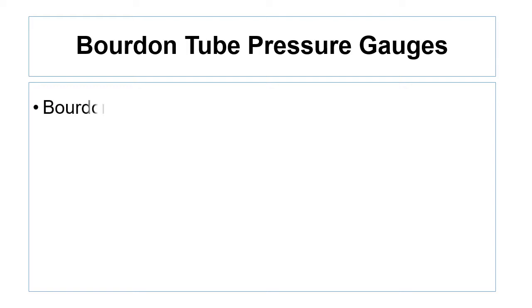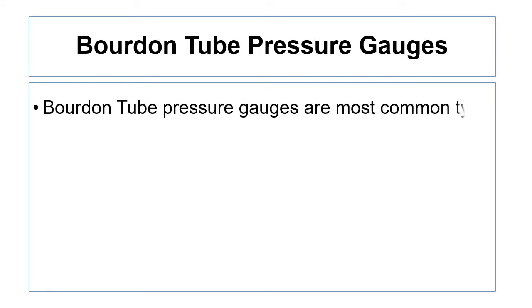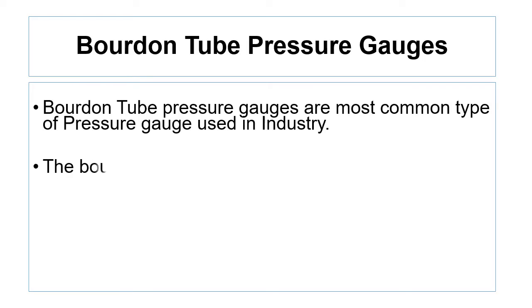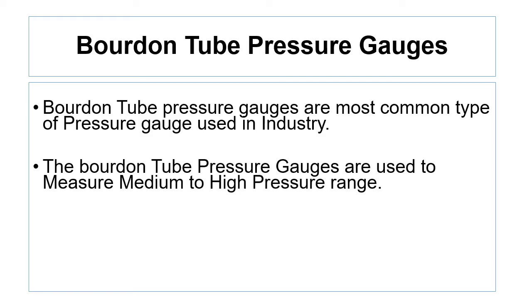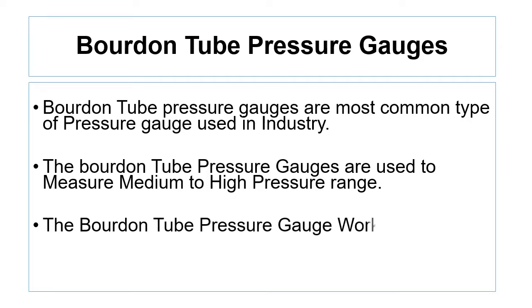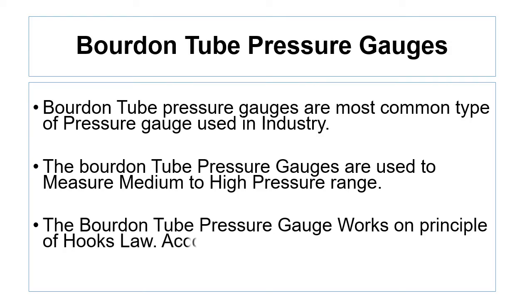Let's discuss the first pressure gauge — the Bourdon tube pressure gauge. Bourdon tube pressure gauges are the most common type of pressure gauges used in industry. They are used to measure medium to high range pressure. The Bourdon tube pressure gauge works on the principle of Hooke's Law: within the elastic limits, stress is proportional to strain.